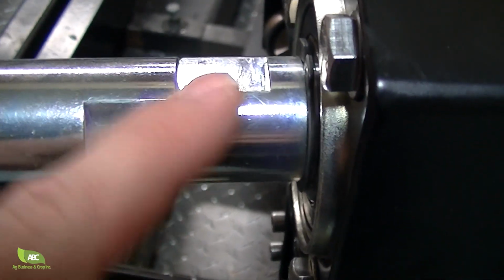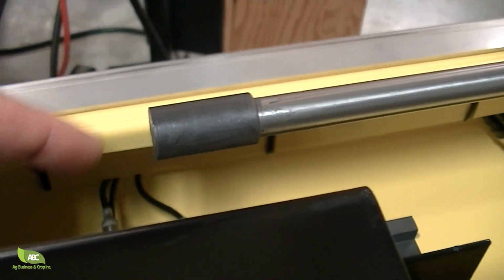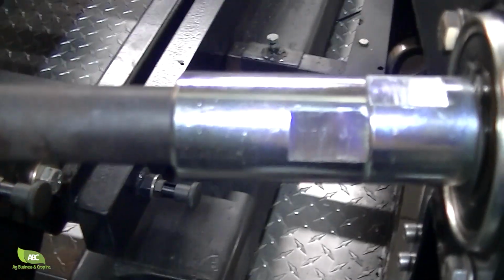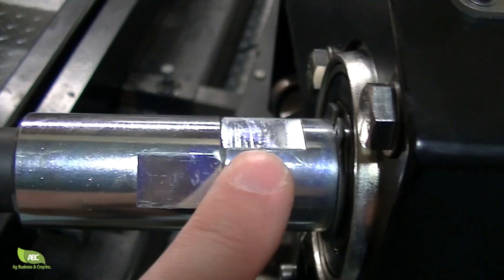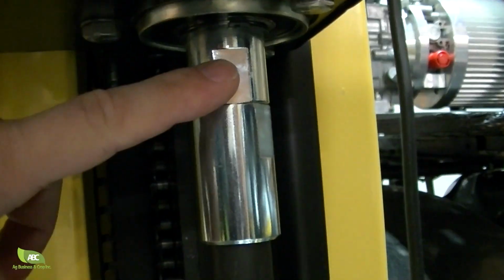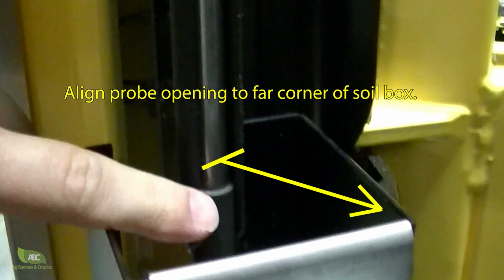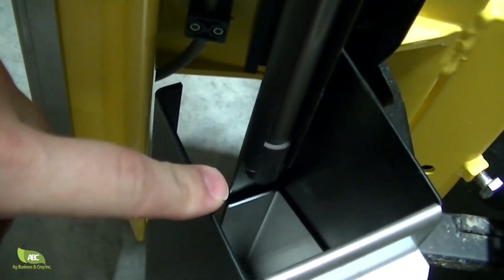You always have to make sure that the thread is all the way in the hub, so you keep the same distance with the ejector all the time. If you keep the probe all the way screwed to the hub, you won't have to worry about this guy here. It's important to check that the probe opening is following this direction inside the soil box. If you need to adjust for some reason, just loosen the probe nut. You can rotate the probe itself until it's in the right position and then lock the nut again. This way you can make sure that the probe opening will always be dropping the sample inside the soil box.